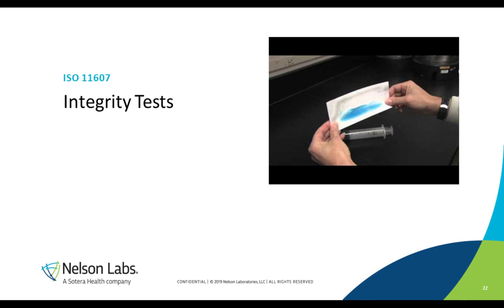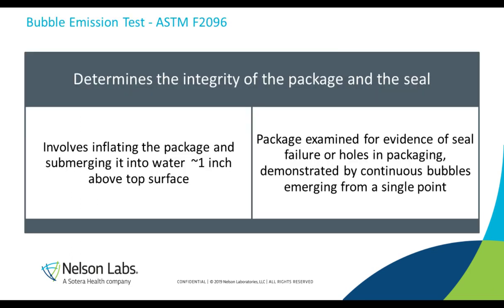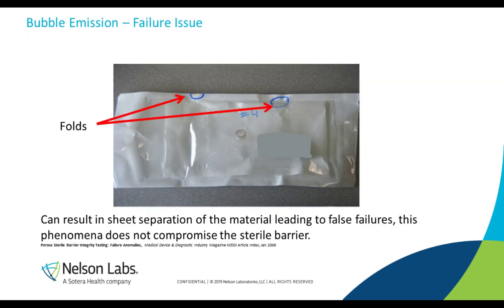Okay, we're going to talk about integrity tests. The integrity test that I selected, which is also the most common, is the bubble emission test. It's regulated by ASTM F2096. It determines the integrity of the entire package and the seal. The way that it works is you submerge the package into water about 1 inch above the surface, and then you inflate it to a validated pressure. The package is then examined for holes or a steady stream of bubbles coming from a single point.